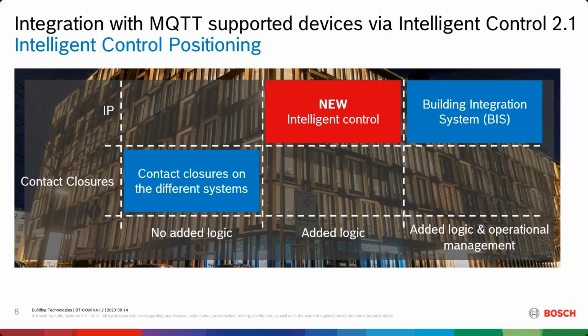Yeah. And then we have the red box, and that is actually something in between. It's not wiring contacts, but it is also not a full-fledged management software with a user interface. It's actually, let's call it logic wiring of contacts. So we have an input device and we have an output action, and we can make logic over software with this. We make basically logical rules. But there is no user interface to operate it. It's an embedded system, and once the logic is programmed, it runs. I think you can very much compare it to maybe a PLC, if you look at this in the industrial field.